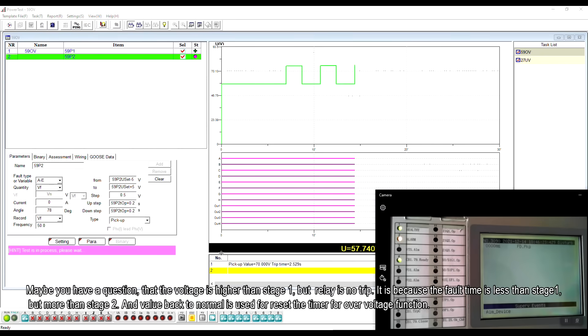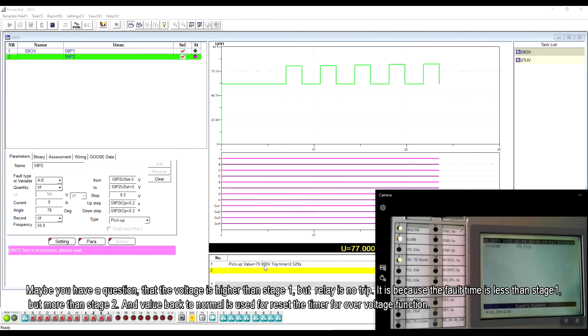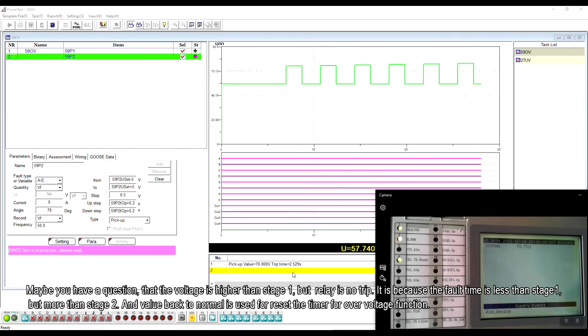Maybe you have a question that the voltage is higher than stage 1 but relay is no trip. It is because the fault time is less than stage 1 but more than stage 2 and the value back to normal is used for reset the timer for over-voltage function.